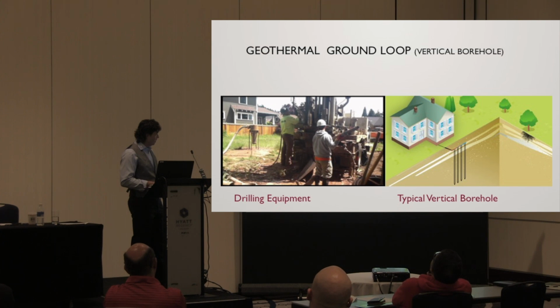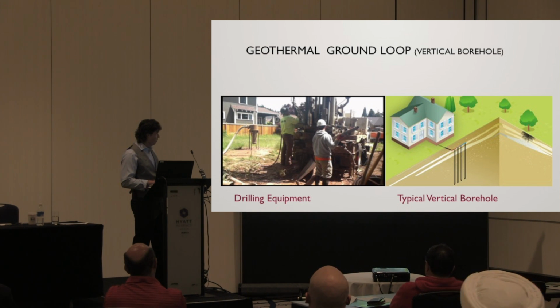When you drill down on average 200 feet here, the ground stays pretty steady. That is until we mess with it and draw the energy out of the ground into the water. And of course the water goes back into the home, into our water-to-water heat pump. One side is water to refrigerant, goes through the compressor, and then on the other side is a water-to-water heat exchanger. We're heating with radiant throughout the house. If that was a forced air unit, it'd just be water to refrigerant to air.